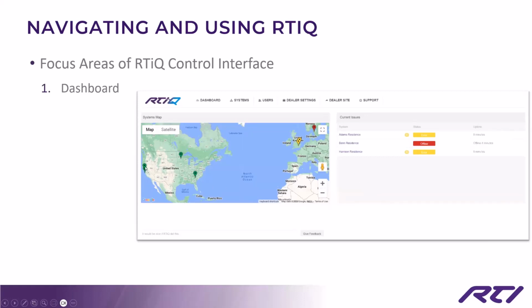Anything that is currently with the green tag is no problem. Anything with yellow has one or more type of error detected. If you happen to see a blue one, that means that is in service mode. And there's more information about service mode in the user guide that we can talk about. And anything in red is that the system or the internet connection that the system is connected to is currently offline. As you can see here, the error versus offline.